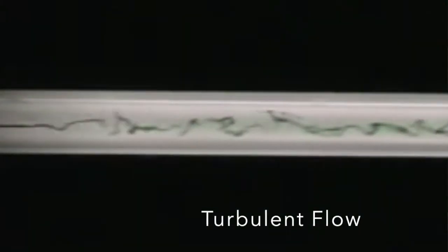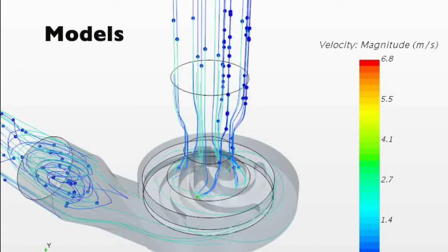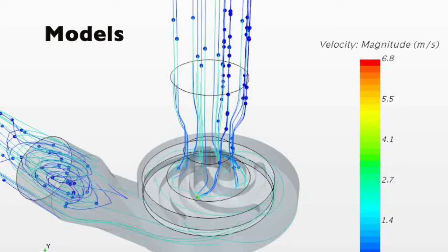For the simulation in CFD, we have to make some assumptions. The first one was that all the fluids we're going to simulate were liquid. Also, because of their incompressibility, we made the constant density and segregated flow. We calculated the Reynolds number, and they were turbulent. Also, we assumed gravity to orientate the pump. And finally, we assume a steady flow because the idea of the pump is not to have accumulation inside of it. After having the assumptions done, we continue with the selection of the models.